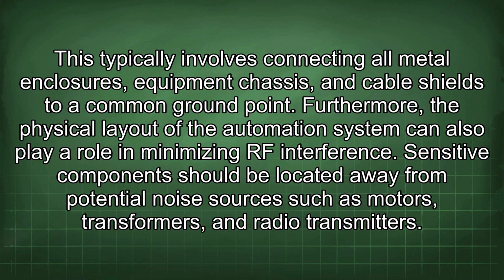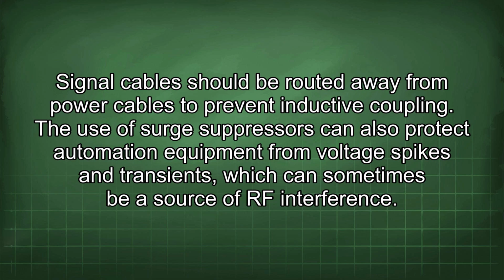Furthermore, the physical layout of the automation system can also play a role in minimizing RF interference. Sensitive components should be located away from potential noise sources such as motors, transformers, and radio transmitters. Signal cables should be routed away from power cables to prevent inductive coupling. The use of surge suppressors can also protect automation equipment from voltage spikes and transients, which can sometimes be a source of RF interference.